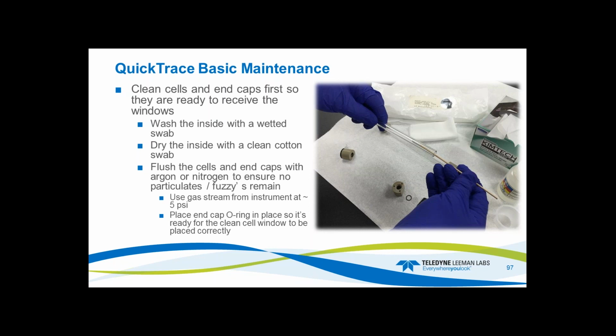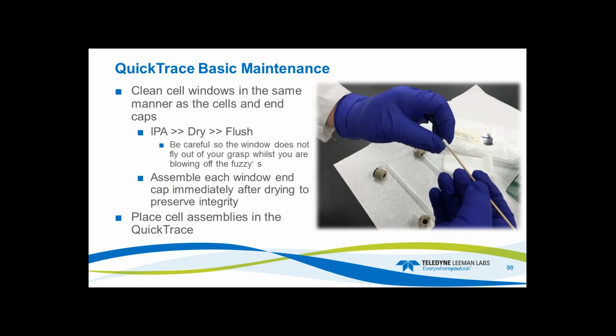And then you can blow off the fuzzies with about 5 psi or so from the back of the instrument. Disconnect that line. Be careful so you don't lose any components. Same thing for the cell windows. IPA, dry flush. Again, be careful so you don't lose the window when you're blowing them off. And then assemble each window and end cap after drying and in the same order you took it apart, and then replace the cell assembly.